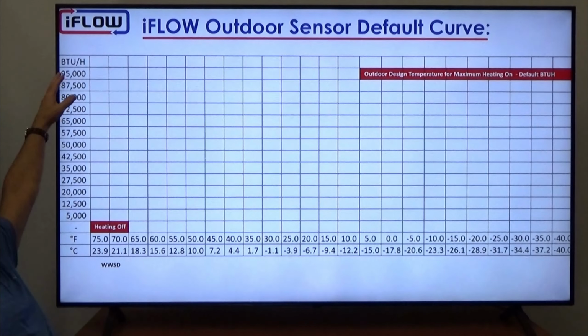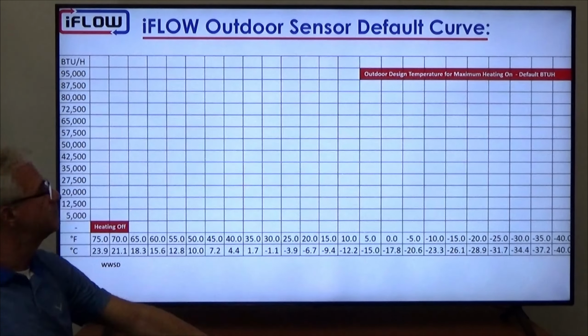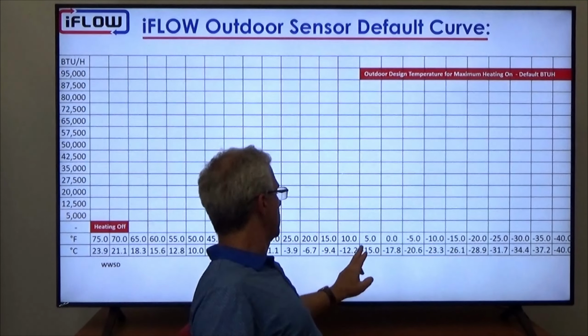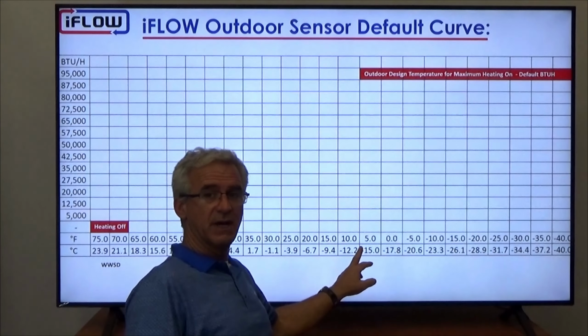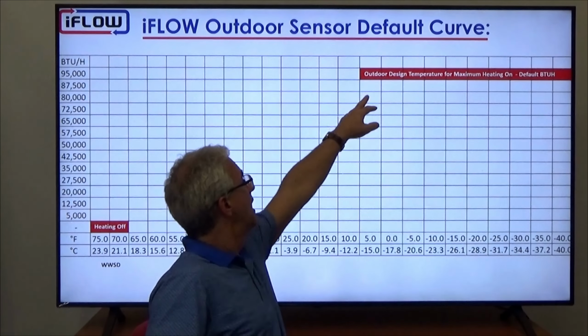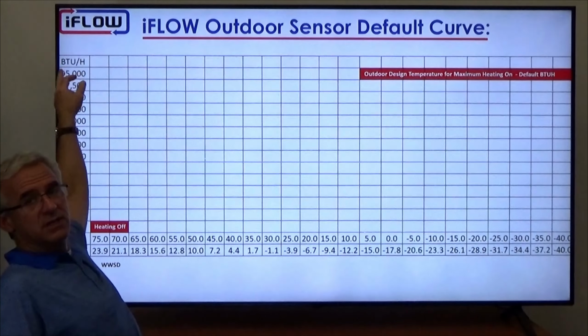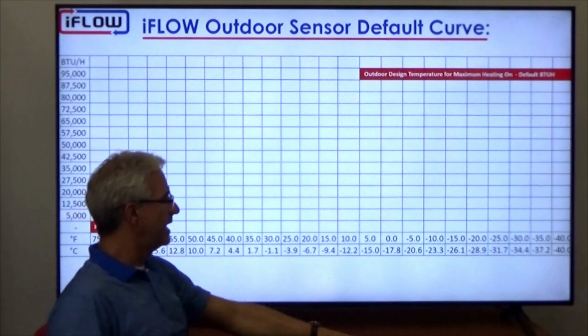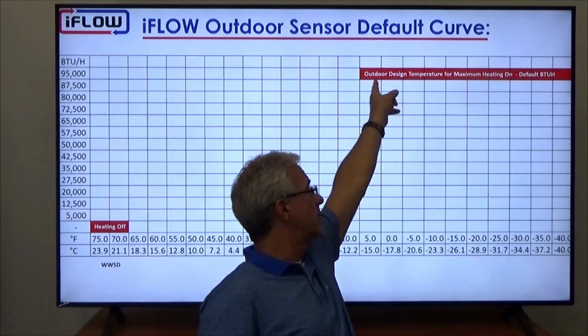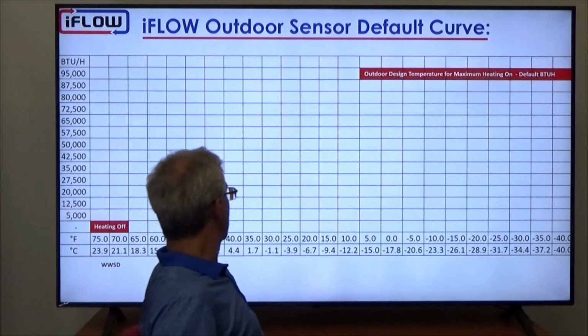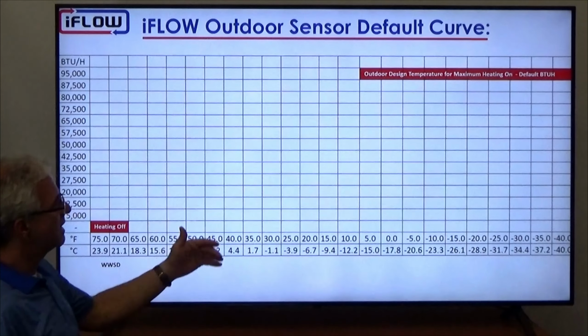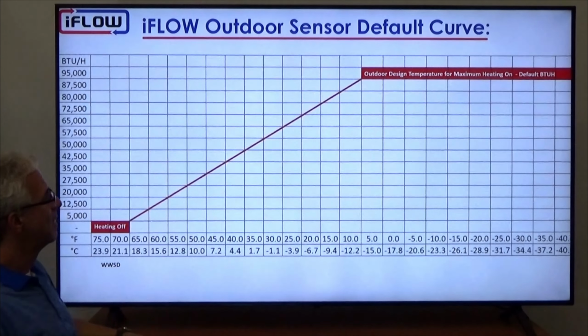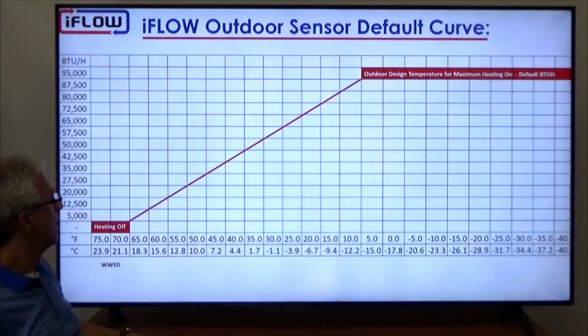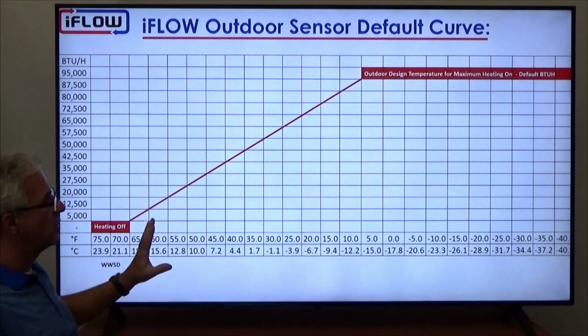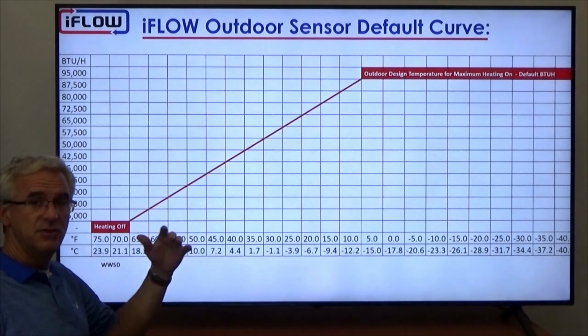For example, we're looking at this 95,000 BTU unit. This is our 18,000 series unit. It can deliver 95,000 BTUs worth of heating. And when does that happen? Well, if the outdoor temperature hits minus 15 Celsius or 5 Fahrenheit, then that's when we deliver 95,000 BTUs. At any temperature colder than that, we will continue to operate at maximum. So we come up and then run at maximum. Once we have those 2 points, we create a slope. On this slope is where the unit will target the BTU delivery.